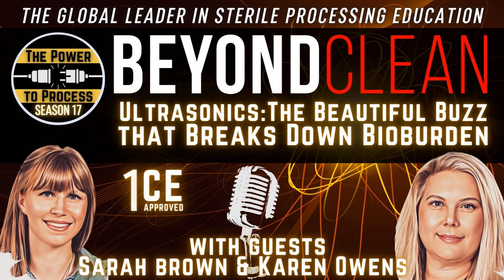So actually, in my mind, that's kind of a really simple question. As most people know, ultrasonic cleaning is appearing now in more and more manufacturers' IFUs. It's required now for most orthopedic and neuro instrumentation, as well as other complex devices. It's not typically required for more basic instrumentation, but it's always best to refer to the manufacturer's IFU for the instrumentation at your particular facility and to confirm what's required for your devices. And the reason I say it's kind of a simple question is because really the bottom line is, if the IFU for the device that you're reprocessing requires ultrasonic cleaning, then you should have one in the department and you should be using it. IFUs are not optional.